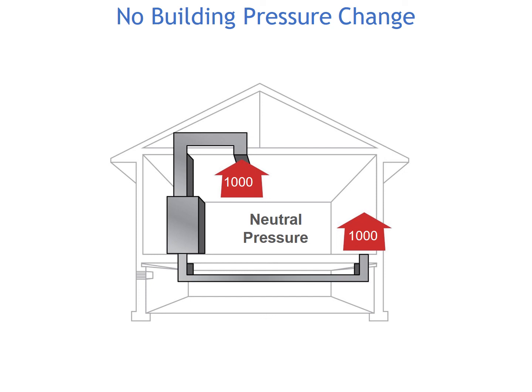So if we're talking about air pressure within the building and we have 1,000 CFM going to the return, then it goes through the unit and 1,000 CFM comes out of the supply, then the system is going to be in perfect balance. It's not trying to pull or push air from any other areas other than within the building envelope itself. So let's use that as a basis as we start discussing some of the next couple of slides.